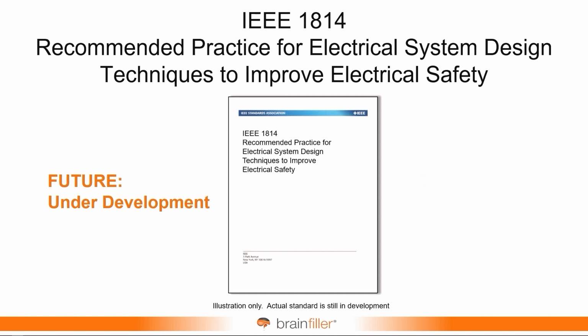There's another standard, and this really isn't part of NFPA 70E, but I just want to mention it for your information. It's called IEEE 1814. It's under development. It's quite a ways away from being completed. But when this is completed, it's going to be a recommended practice for electrical system design techniques to improve electrical safety. So it will basically complement what's in Annex O.